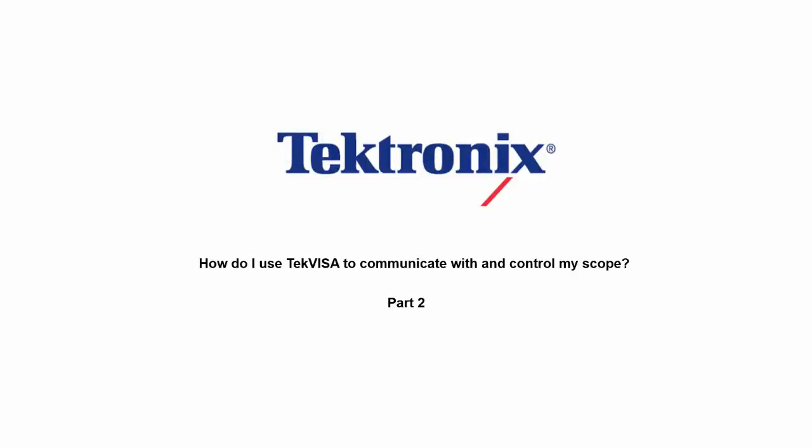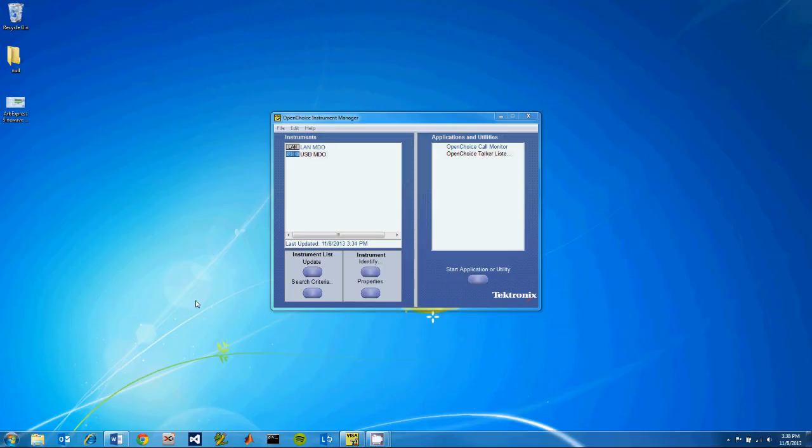Today I'm going to walk through how to send commands to an instrument using TekVISA. This is the second part of a three-part series on TekVISA. In order to communicate with and control the scope, you can use OpenChoice Talker Listener.